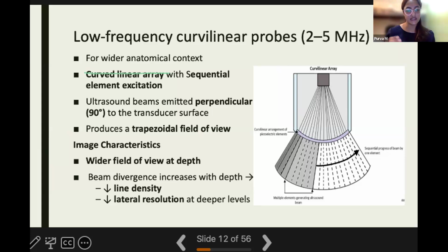Now, this beam divergence that happens at depth has certain fallacies also. It is giving you better penetration, allowing you to look deeper, but it has certain fallacies. It will reduce the line density, which, as I'll be discussing in the subsequent slides, is an important function to have. And also, it will decrease the lateral resolution at deeper levels. So you might not be able to differentiate between two objects which are placed very close together.